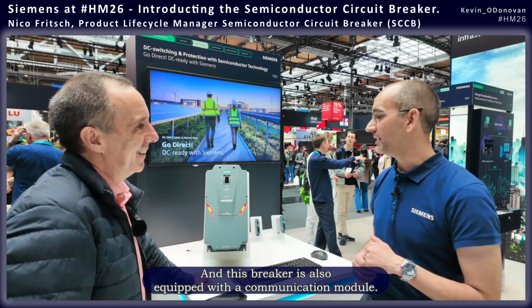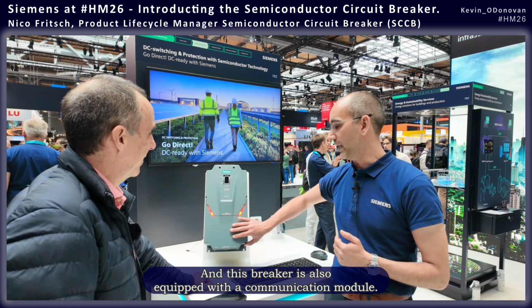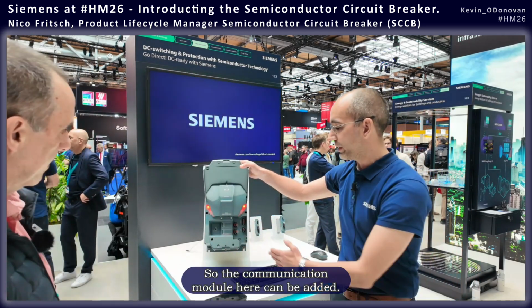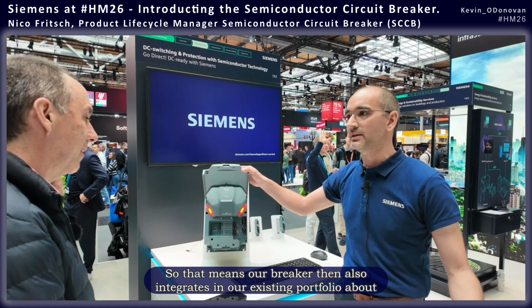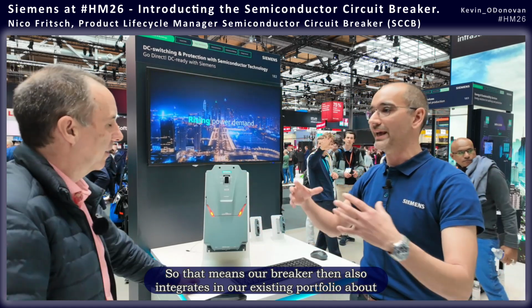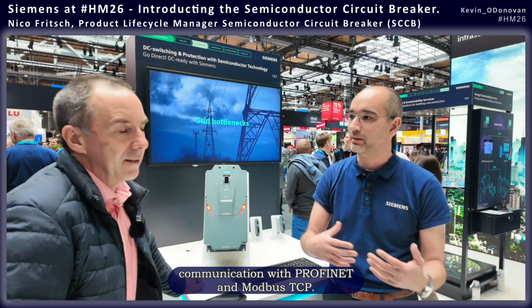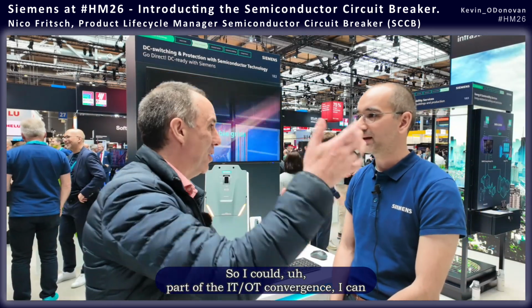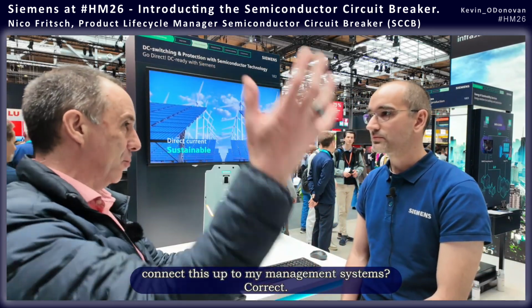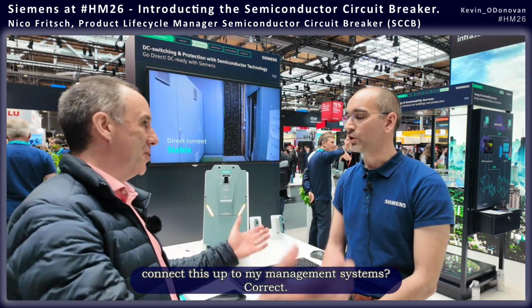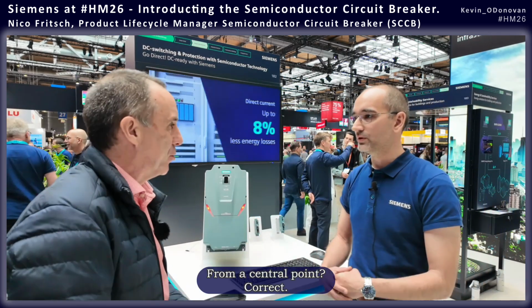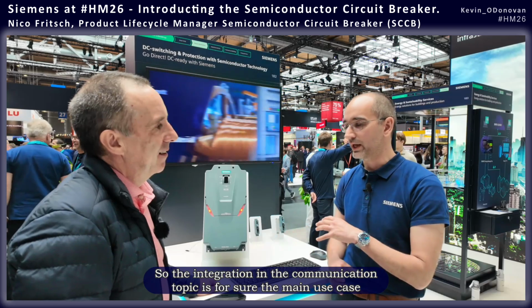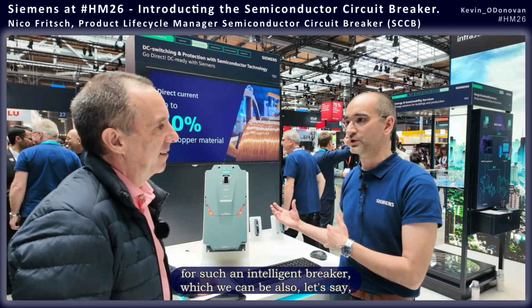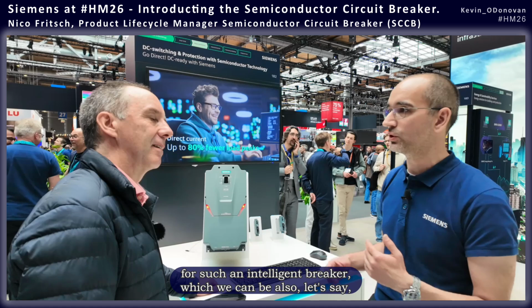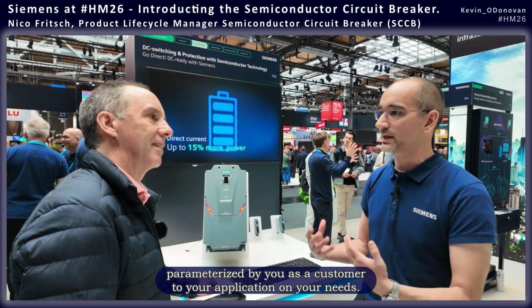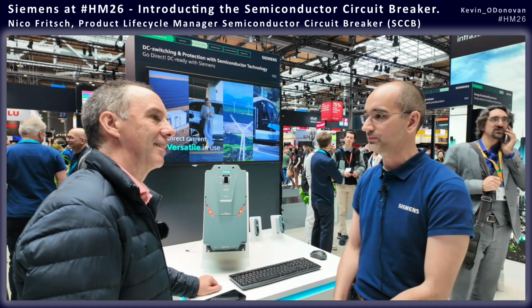This breaker is also equipped with a communication module, which can be added. That means our breaker then also integrates into our existing portfolio with communication via Profinet and Modbus TCP. As part of IT/OT convergence, I can connect this up to my management systems and manage everything from a central point. The integration in communication is for sure the main use case for such an intelligent breaker, which can also be parameterized by you as a customer to your application and your needs.